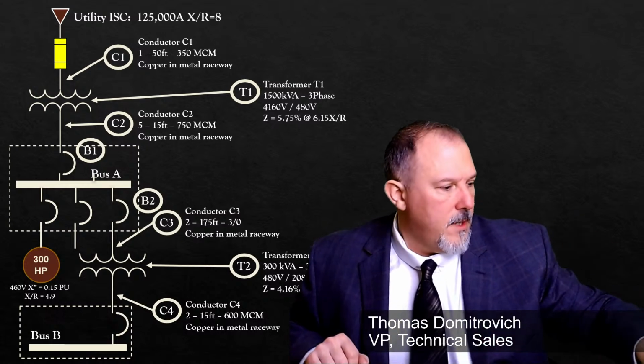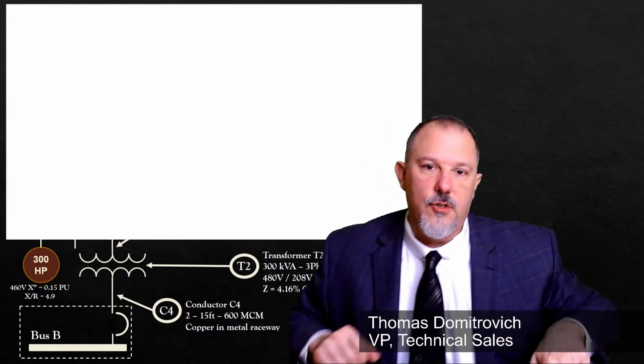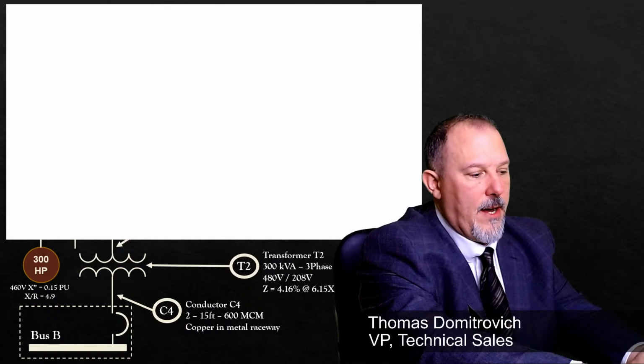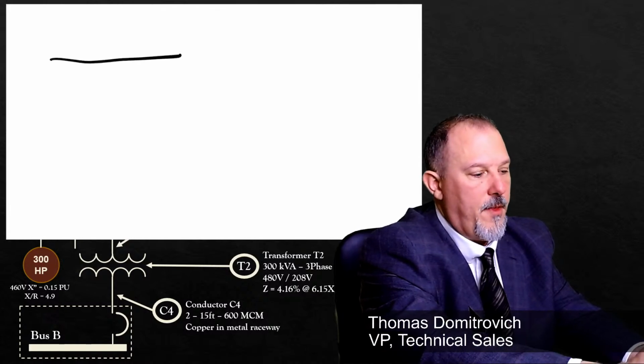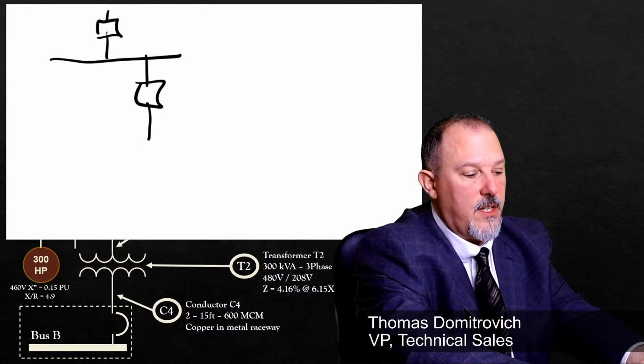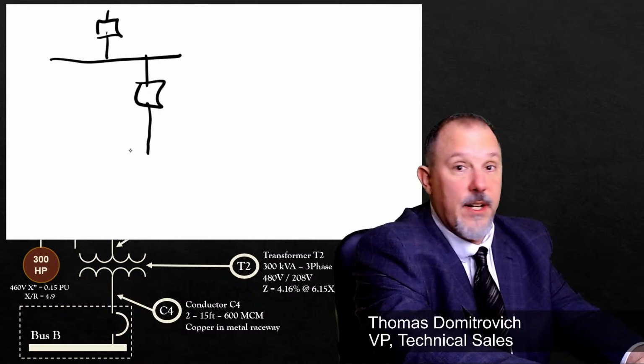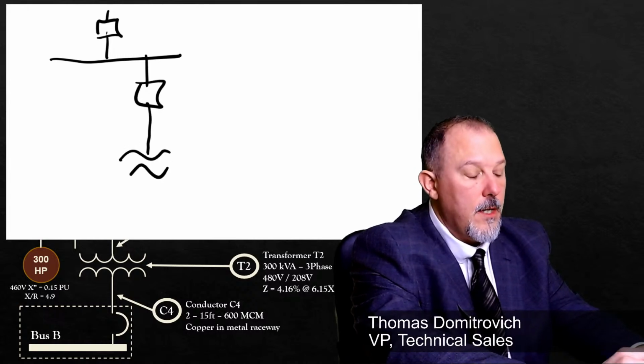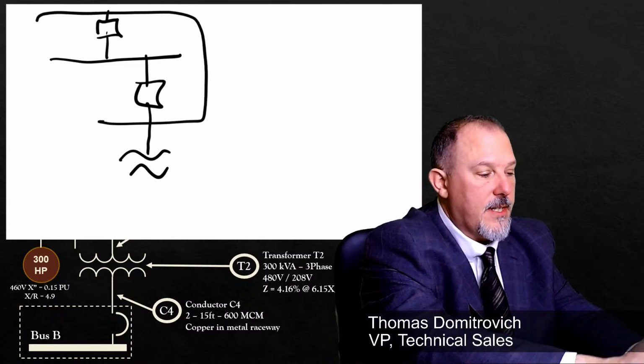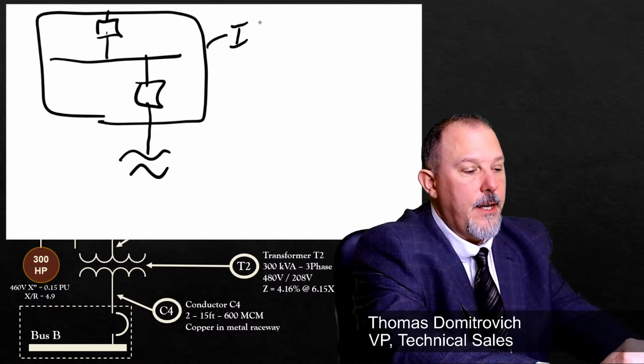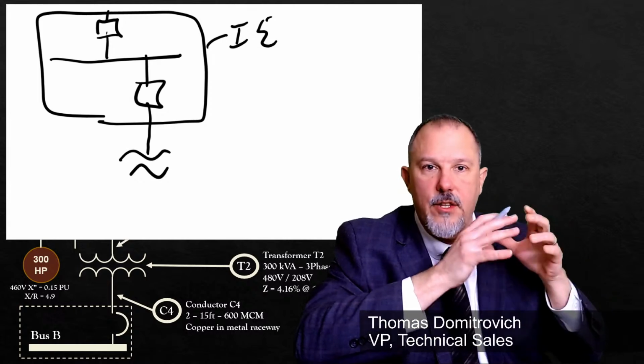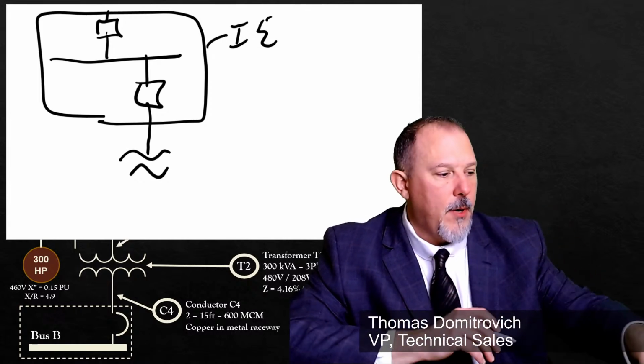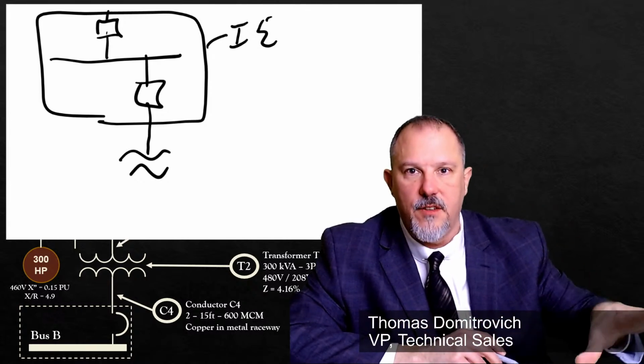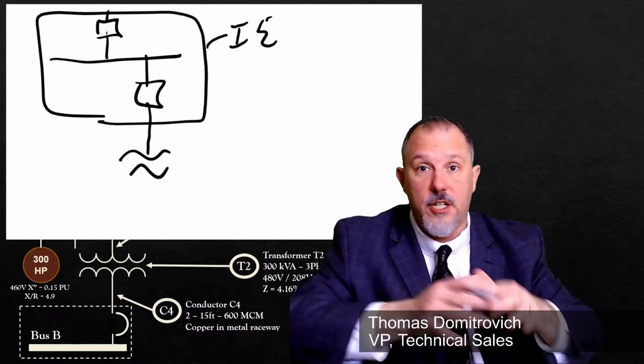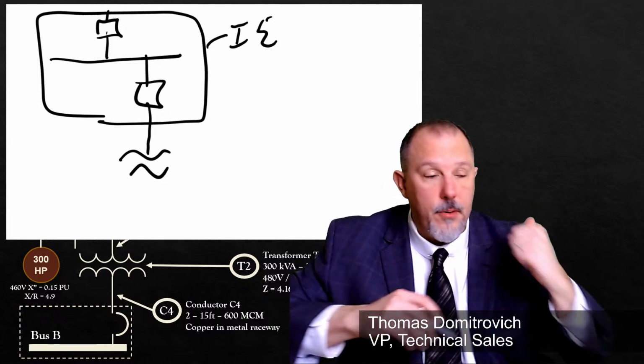It's easier if I just draw it on the whiteboard. So remember, I have a panel with a main breaker in it, and I have a feeder circuit breaker that's feeding a transformer, right? And all of these are in the same enclosure. Now, the incident energy in that switchboard, that 2000 amp switchboard, is not dependent upon that main overcurrent protective device. Why? Because I have to think about line side propagation. If you don't know what that is, watch a previous edition of this.